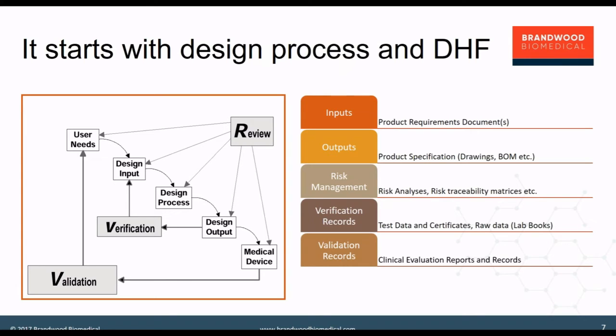Validation records also, obviously. We discussed the validation process earlier in this slide. So the validation in the context of a medical device will include several things, but the main element expected as part of that process is the clinical evaluation report.